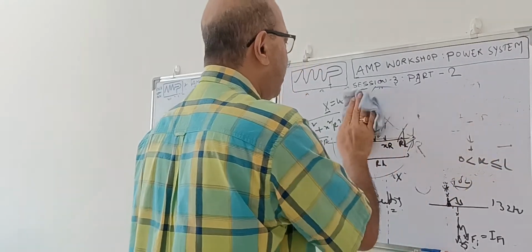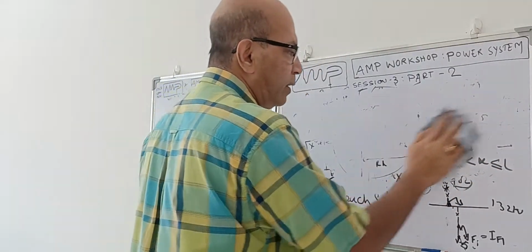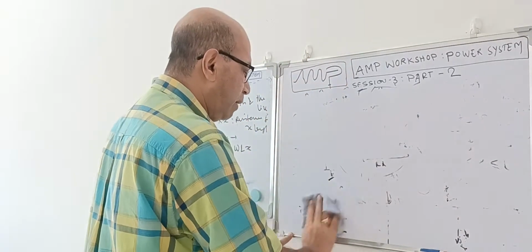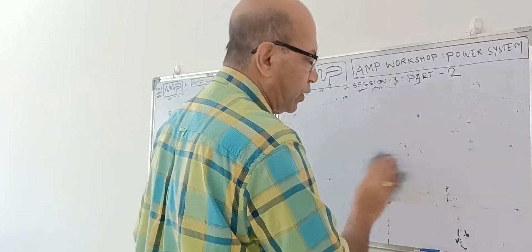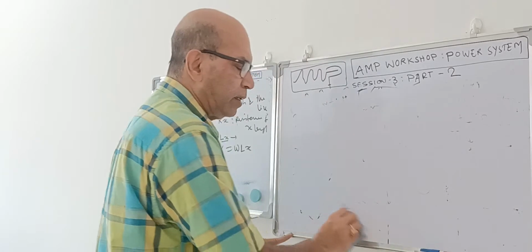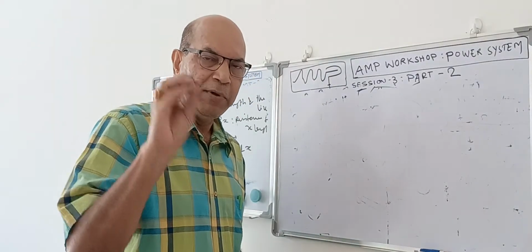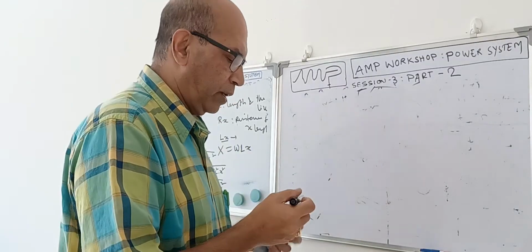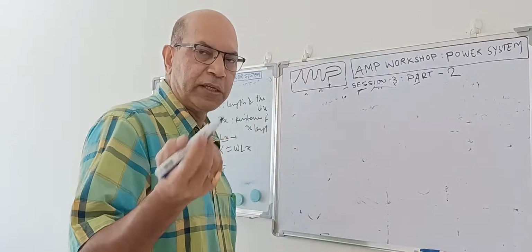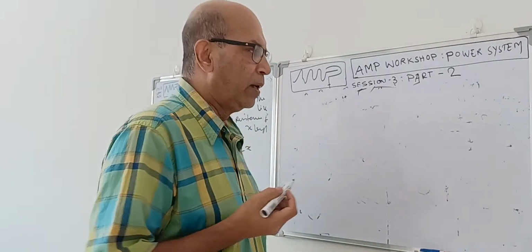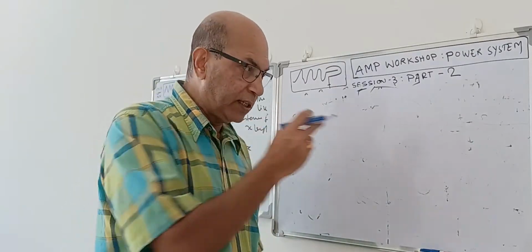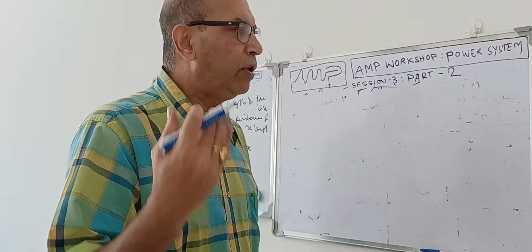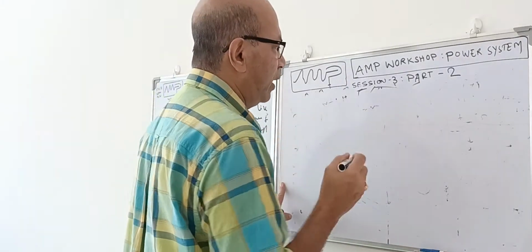Now about this second part, these are the two. This is also non-unit protection. Now we said that we will use another type of protection scheme which we call a unit protection scheme, where the operation is limited within a restricted area. If the fault is outside of that area, it will not operate. We showed one example, the Merz-Price current differential scheme. That is one of the unit schemes. Distance protection is a non-unit protection, but with a carrier aided facility, we can convert it to a unit protection. That we will discuss. Now come to the differential unit type protection.